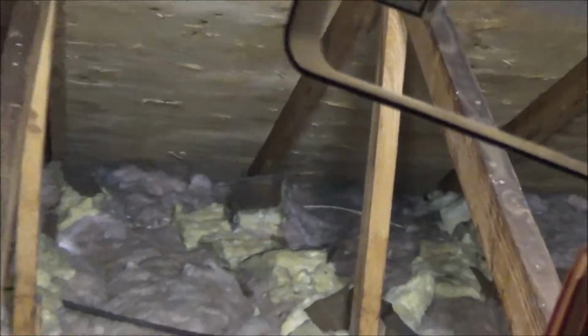All the way at the end, what's supposed to be happening, when you see where the plywood is, where the roof comes down to the wall line, there's supposed to be baffles in there to allow air from the vent to come up into the attic.